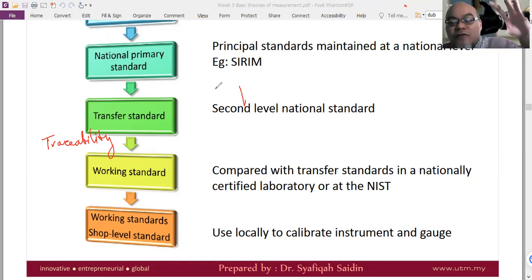It means what we measure at the shop level should conform eventually to the international level standard. Its accuracy can be traced to the international level standard. It doesn't stand alone. So if your instrument or sensor is never calibrated, then it cannot be traced. It cuts the link. There is a missing link in the measurement. That is why, if it is for your own use, maybe it's okay.